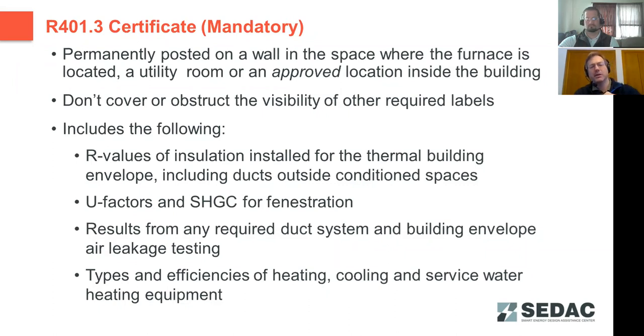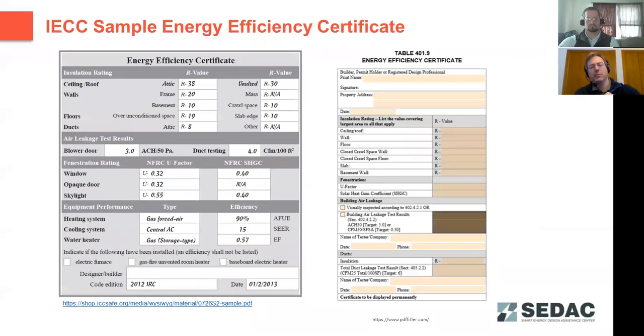So next here we see some examples of building labels. There are many other formats that this can be in, but here are two templates. If I received this certificate on the left, I'd be a little bit skeptical. Now, this is based on a previous code edition, but all of these values are exactly the code minimum. So the fact that the blower door test and the duct test came in at exactly 3 ACH and 4 CFM, I would be fairly skeptical of this label.